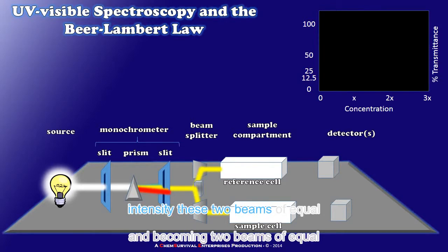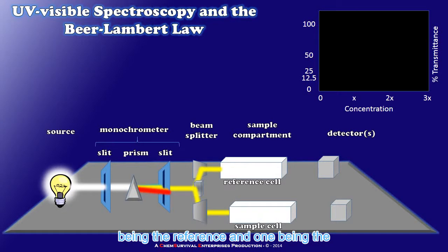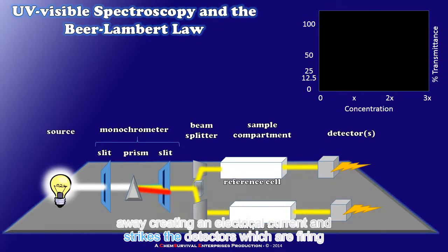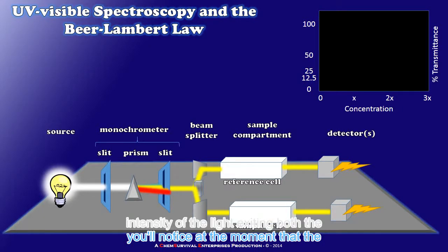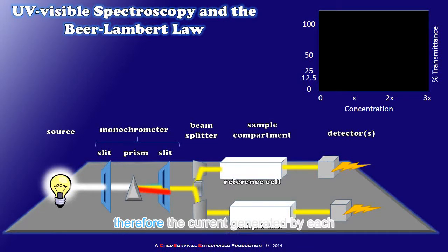These two beams of equal intensity will traverse a cell, a different one for each of course, one being the reference and one being the sample cell. As the beam exits these cells it strikes the detectors which are firing away creating an electrical current. And you'll notice at the moment that the intensity of the light exiting both the reference and sample cells is identical therefore the current generated by each detector is identical.